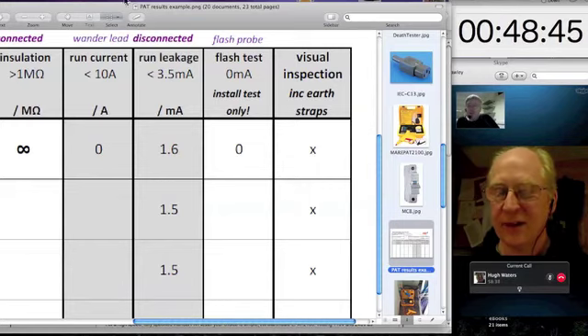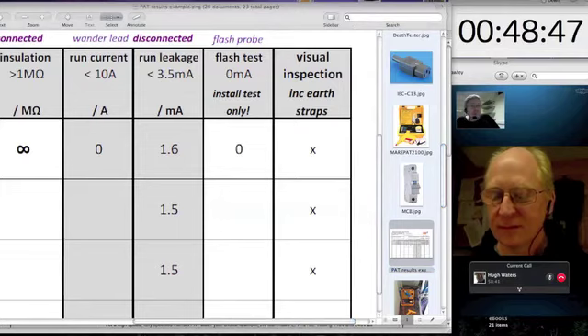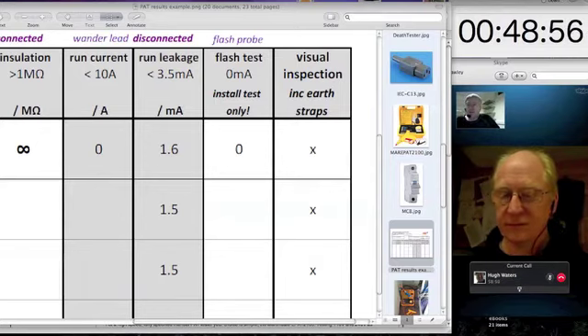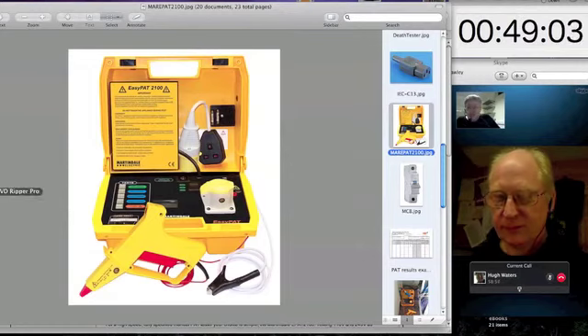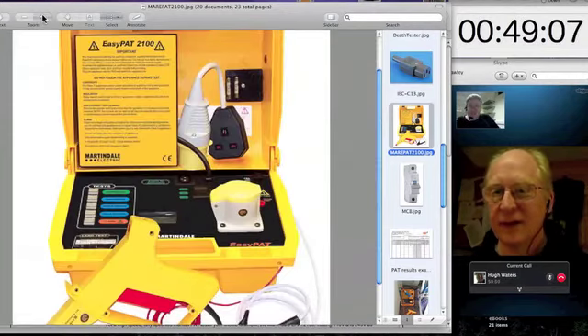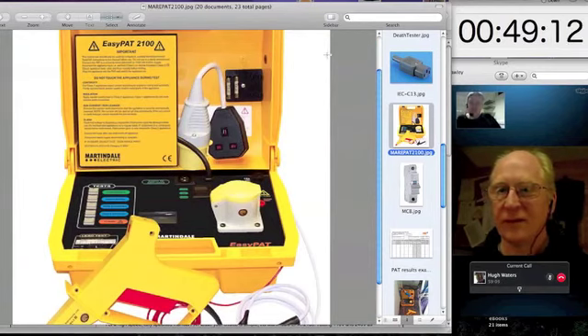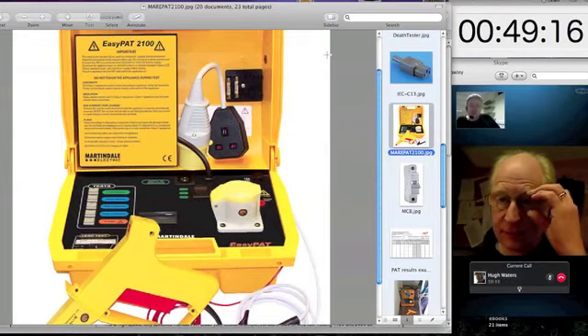So it's probably worth mentioning what the various tests are on a PAT tester. Yes, I think that's a good idea. What the testing protocol is, again, this is not legally mandatory, but you would have such a hard time in court if it had been shown you hadn't done your best. If you'd commissioned a new build, a new machine room, and you just hadn't paid for this, or as the installing engineer, you hadn't gone to the extra step of doing this and certifying it to the customer.